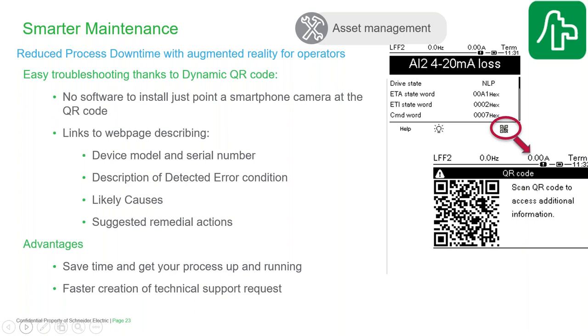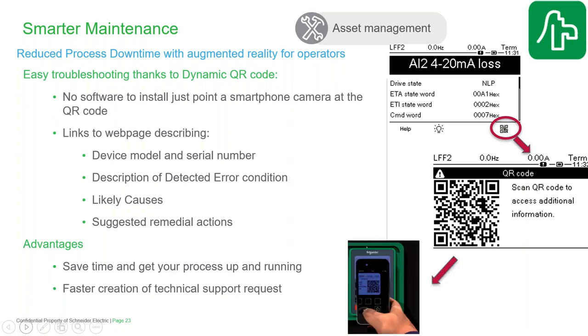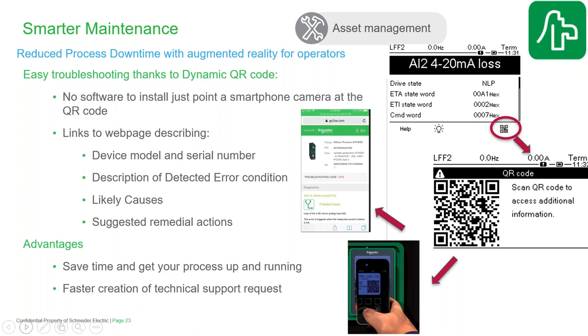Now, if you take your smartphone out and scan that QR code, and by the way, you can do that here if you've got a camera handy and pointed at the screen, that will pop up a little link window, which if you tap on it, will take you to a website. That website is specific to this drive and error condition. It will tell you the drive model number and the drive serial number, which is great if you're calling a tech support line, because those are always the first questions they'll ask.